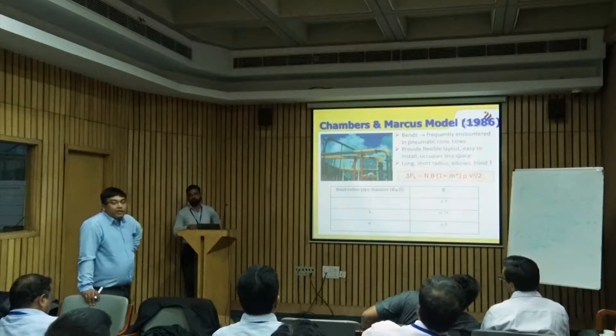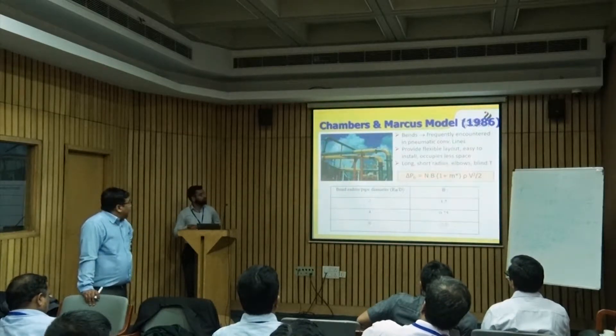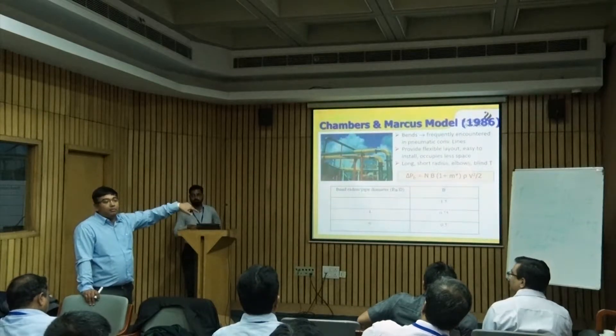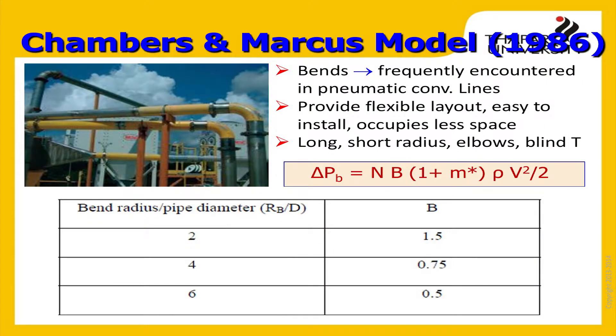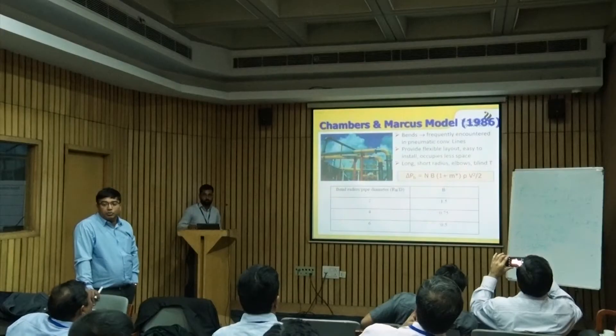You've got to multiply the number of bends you have in the line with a factor B, which depends on the radius of curvature to diameter ratio. I have given a table here — R_b is the radius of curvature of the bend. You can have a short radius bend or long radius bend; divide that by the pipe diameter. Depending on your R/D, you have a different value of B. You put that B in the line, multiply by the number of bends, then by (1 + M*) — where M* is the loading ratio — into density of air times velocity squared divided by 2. That's your pressure drop for the bends.